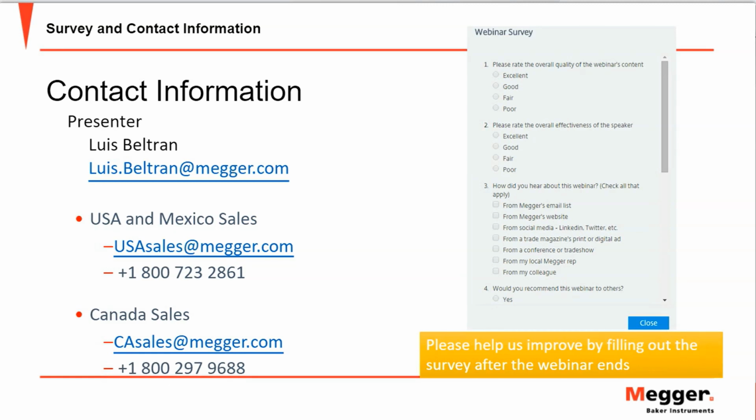And lastly, we have a question for Abel. Can a surge test be done from the circuit breaker instead of motor leads? And are there any differences in the accuracy of the results? Well, like any insulation test, the more elements that you add in series with the device that you're testing, the more capacitance that you're adding, and therefore you need a larger machine, right? That said, yes, you can do the test from the circuit breaker, as long as the circuit breaker is insulated.